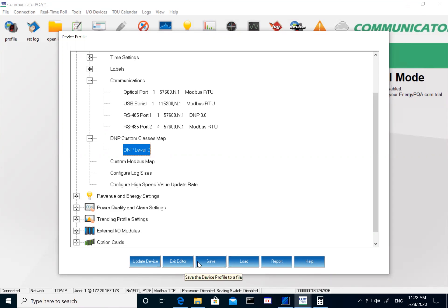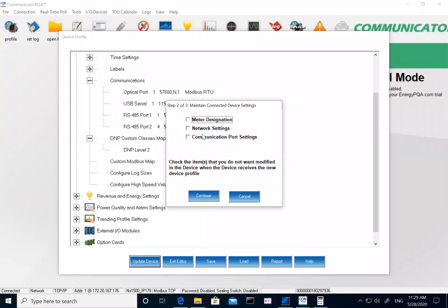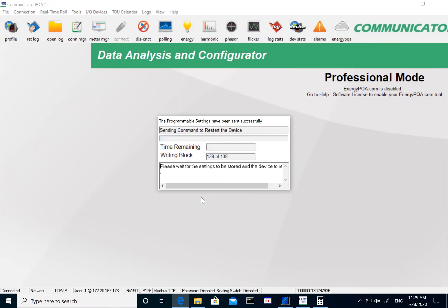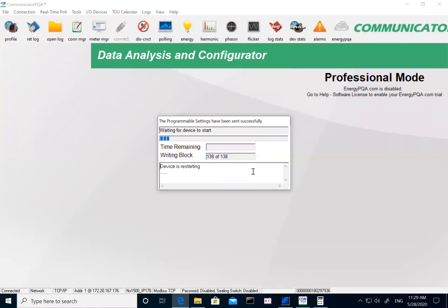Once you're done making all changes, you can save them to work on later offline, or update the meter. When you click Update, it gives you the option to leave unchanged settings unchecked. If you want everything updated, hit Continue and that will update the meter with the new DNP settings, after which the meter will reboot. Once it's rebooted, the software will reconnect and bring up the updated profile.